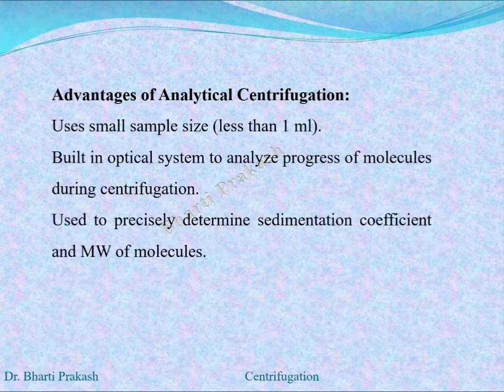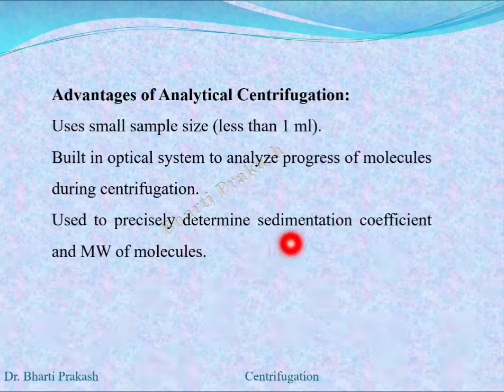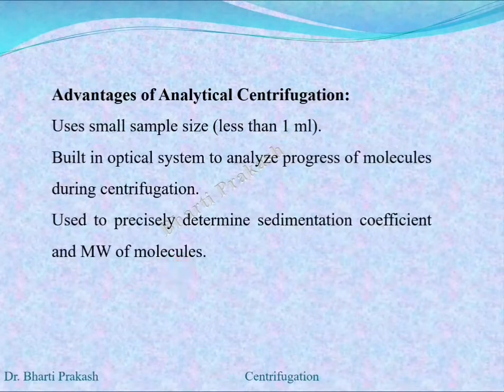The advantages of analytical centrifugation: it can use a very small sample size — less than 1 ml. The built-in optical system is used to analyze the progress of molecules during centrifugation, and these instruments are used to precisely determine the sedimentation coefficient and the molecular weight of the molecules.